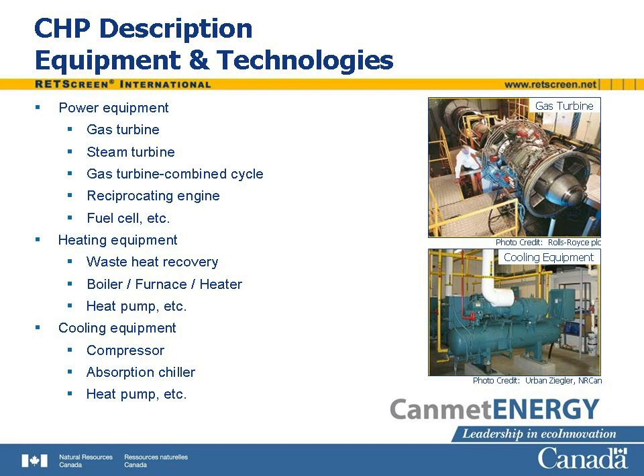A second essential component of CHP plants is the waste heat recovery unit, which collects the waste heat from the power plant so that it can be delivered to heat loads. The nature of the waste heat recovery system depends on the type of power plant, the required temperature, and the characteristics of the heat load. Most applications requiring high temperature heat will demand steam, which can be produced using the hot exhaust gases of a gas turbine or reciprocating engine, requiring a heat recovery steam generator. Steam turbines can sometimes provide low-grade steam at their exhaust port, or it can be bled from the turbine as necessary. When only low temperature heat is available, it can be used to preheat water destined for steam generation. Low temperature heat can be conveniently transported from the plant to loads in streams of hot water, where a heat exchanger recovers the waste heat. The hot water can be used directly, such as for domestic hot water or space heating, and the temperature can be raised somewhat by a heat pump if necessary.